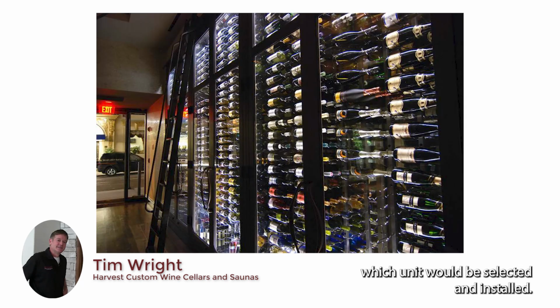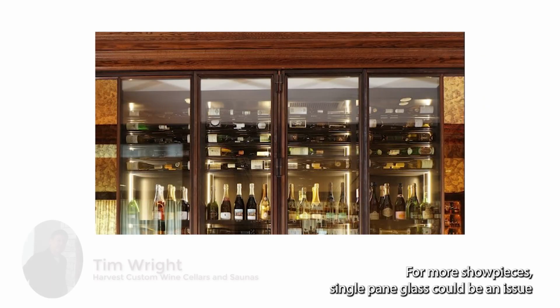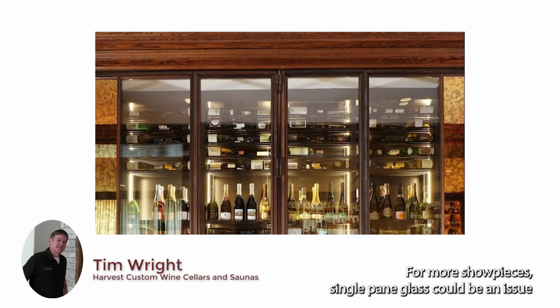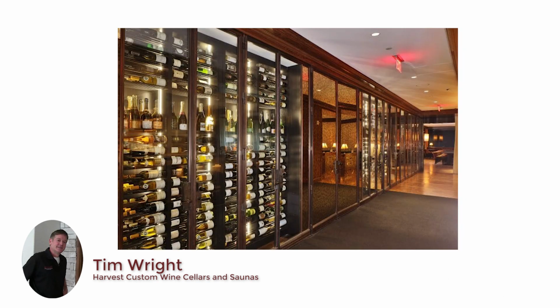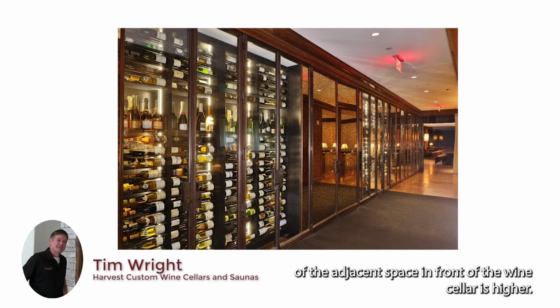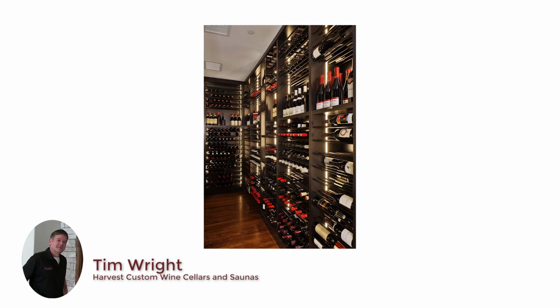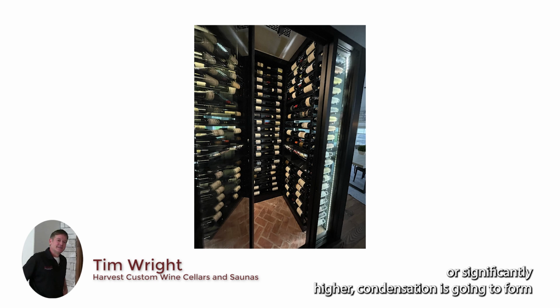For more showpieces, single pane glass could be an issue in humid locations, meaning that if the ambient dew point of the adjacent space in front of the wine cellar is higher or significantly higher, condensation is going to form and the glass will fog.